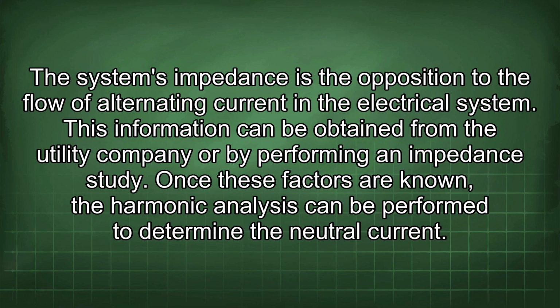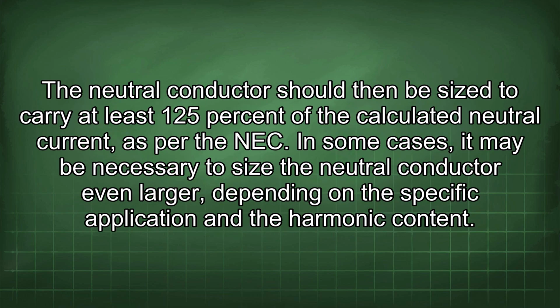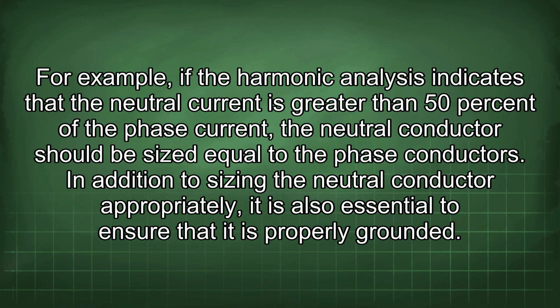Once these factors are known, the harmonic analysis can be performed to determine the neutral current. The neutral conductor should then be sized to carry at least 125% of the calculated neutral current, as per the NEC. In some cases, it may be necessary to size the neutral conductor even larger, depending on the specific application and the harmonic content. For example, if the harmonic analysis indicates that the neutral current is greater than 50% of the phase current, the neutral conductor should be sized equal to the phase conductors.